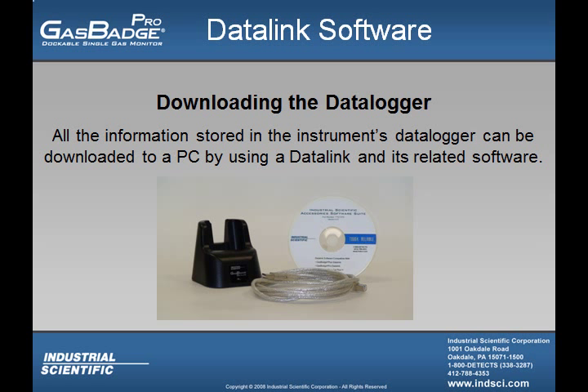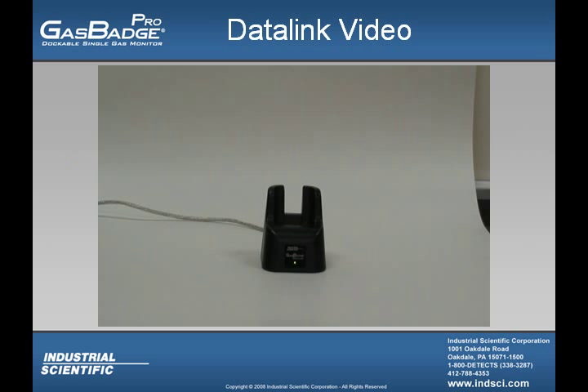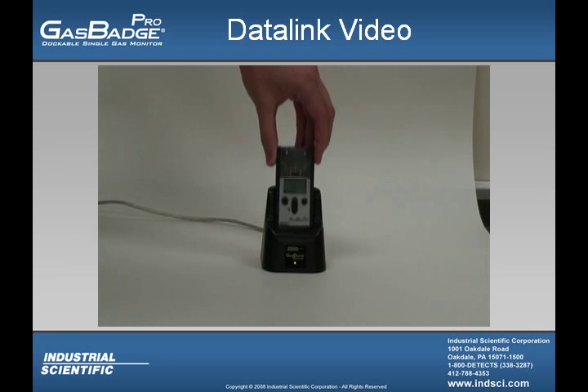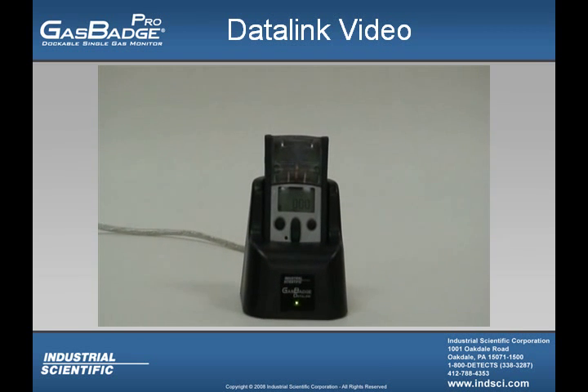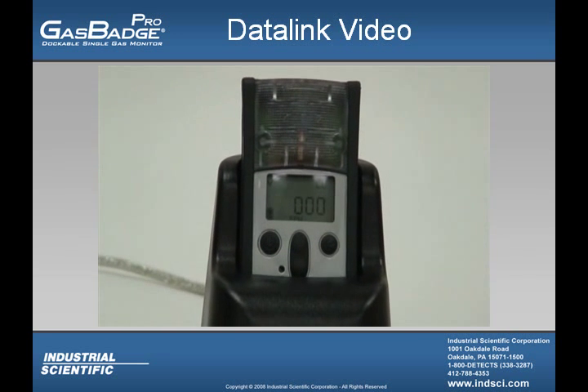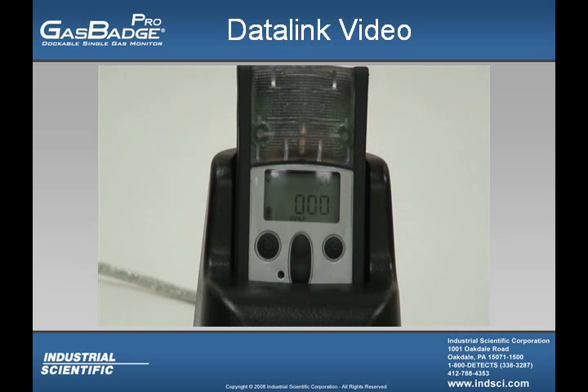The user can easily download the recorded data logging events by using the Datalink accessory and its related software. The video you are now about to see shows how to insert the Gas Badge Pro into the Datalink accessory. It's pretty basic but it's very important to make sure the Gas Badge Pro is facing towards the front of the Datalink.